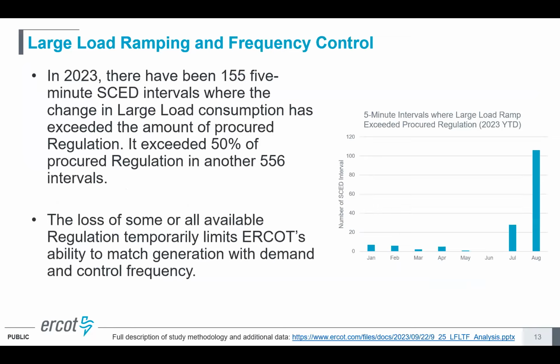We've started to see a noticeable increase in the number of intervals where large load ramping behavior has exceeded the procured regulation. To be clear, I'm not saying regulation was exhausted in all these intervals, because there are other factors like wind and solar ramps and other load ramping behavior. But what's concerning is that we're stepping into a world where large flexible load ramping by itself is enough to potentially exhaust the regulation and limit our ability to control frequency.